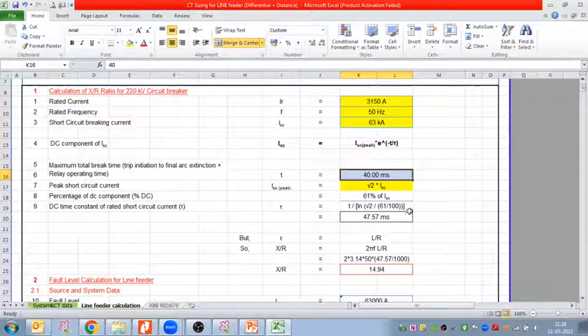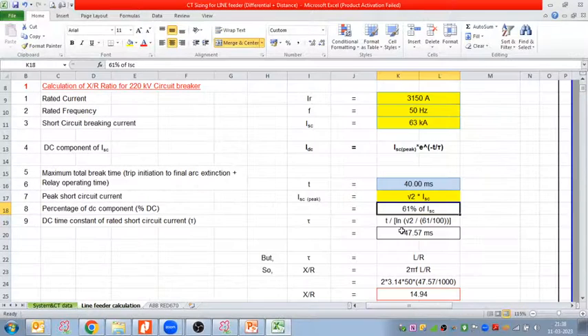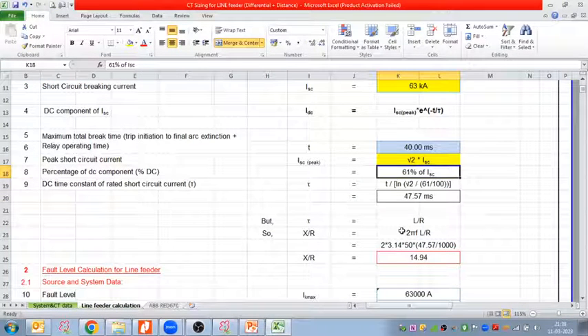IDC would be 61 percent of the ISC, because 61 percent is what my breaker can break. So I am taking the same DC percentage that we have, 61 percent of the ISC. Even though we have already done these calculations, just to refresh the earlier calculations done during the ETAP grid modeling, let us solve this formula.